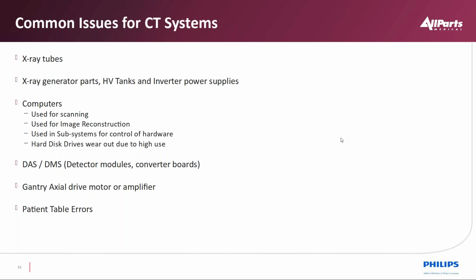Then we have X-ray generator parts, especially the high voltage tanks. We're dealing with 140,000 volts there. And then the inverters that feed those tanks. If the tank breaks down or its high voltage circuits break down, it could put extra stress on the inverters and take them out as well.